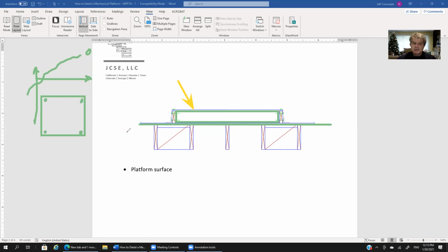So roof surfaces are anything but level. And yet the mechanical unit needs to be sitting on a perfectly level surface. The way we achieve that is by using these 2x6s here, where we're bridging the gap between the roof sheathing and the sheathing that we've laid out for the mechanical unit. We're bridging that with 2x6s that we then shape. So they're going to be shaped, meaning they will be cut. If I exaggerate, they might look something like this.